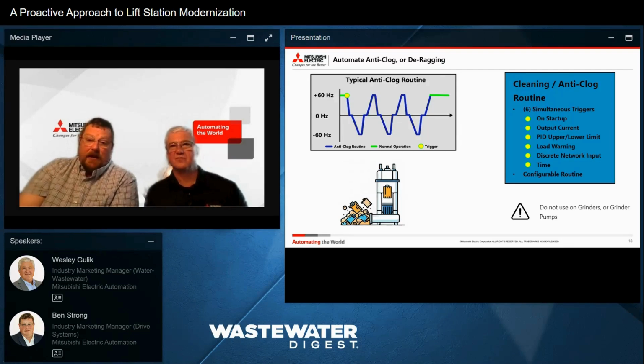But if you also say, every 24 hours of runtime, run this routine. Every time on startup, run this routine. What you can do is proactively remove fouling from that impeller and possibly move things from the suction before they get in and start fouling up your pumps. So we recommend more than one trigger. These are ORs. You could configure all of these triggers. We've had customers that use an input right on the screen with a push button. So if the lift station isn't flowing when it's supposed to be, they go out there and trigger the cleaning routine right by the push button. Some of these people who operate lift stations can tell by sound it's not right.